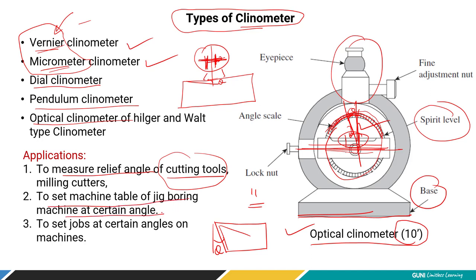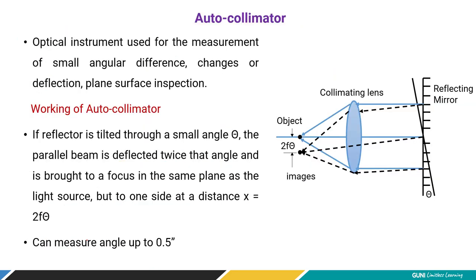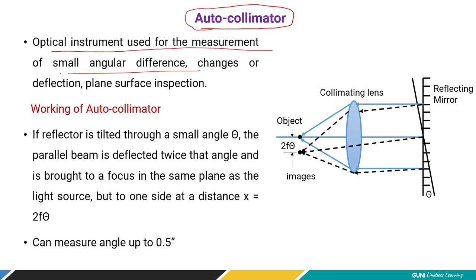The clinometer is also used to set a job at a certain angle on machines. The autocollimator is another angular measuring device. It works on the principle of ray/light reflections, so it is an optical instrument used for measurement of small angular differences — used to measure small angular differences, changes, deflections, or for plane surface inspection.